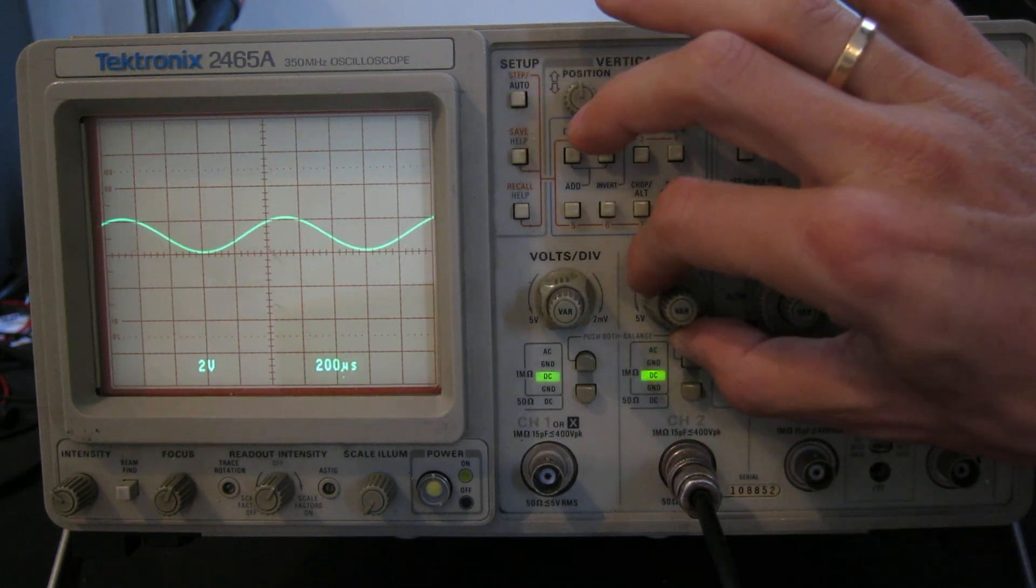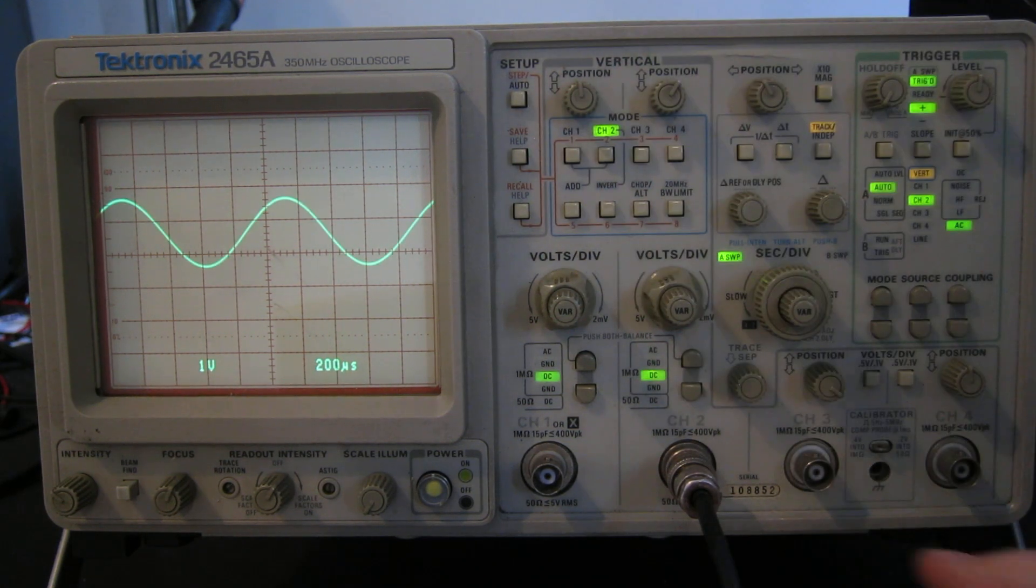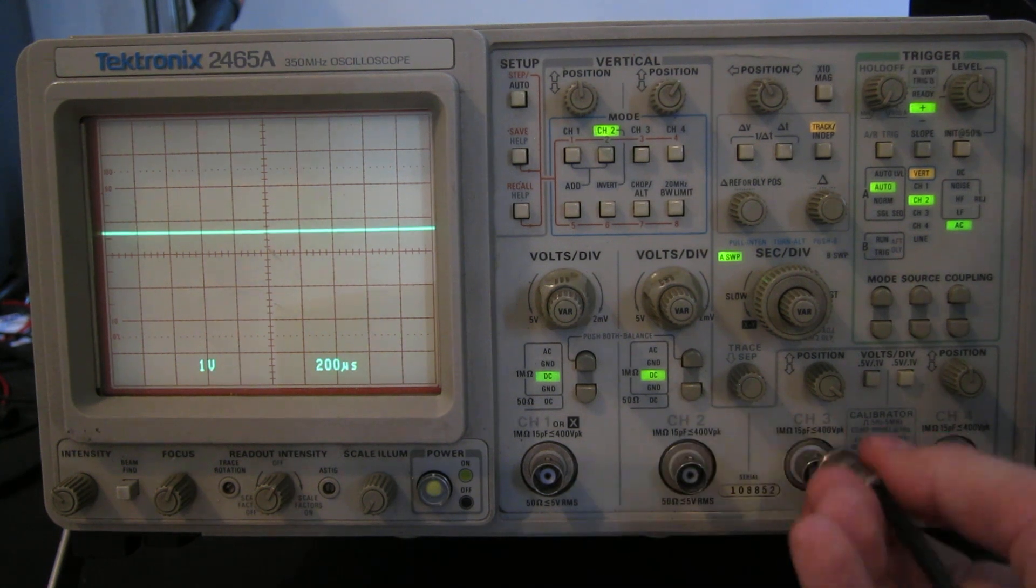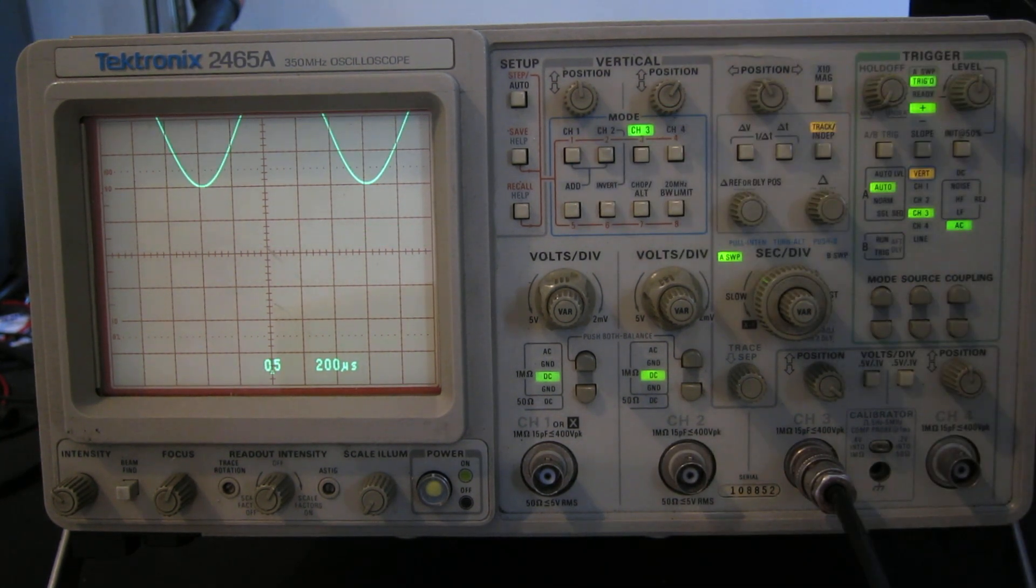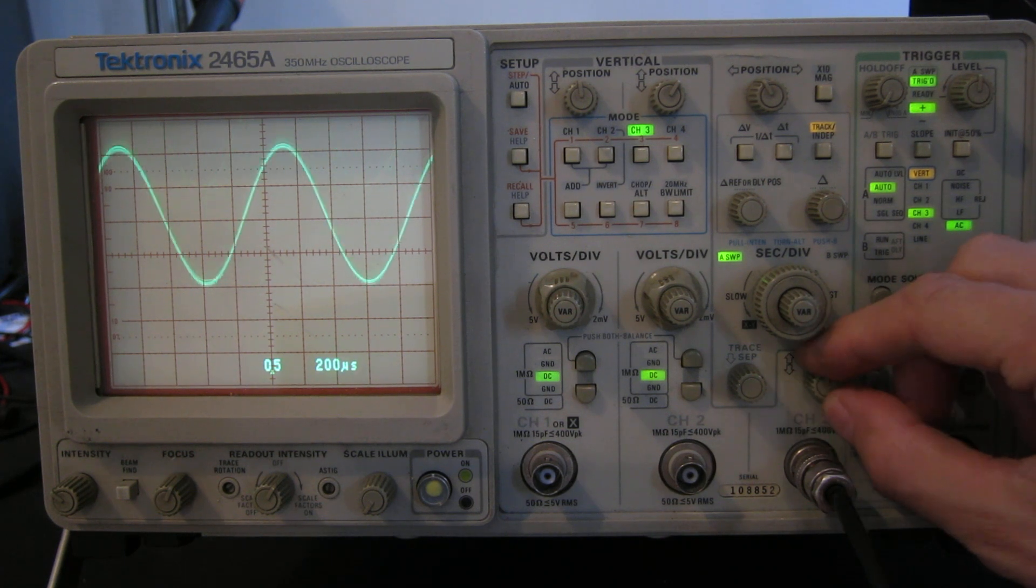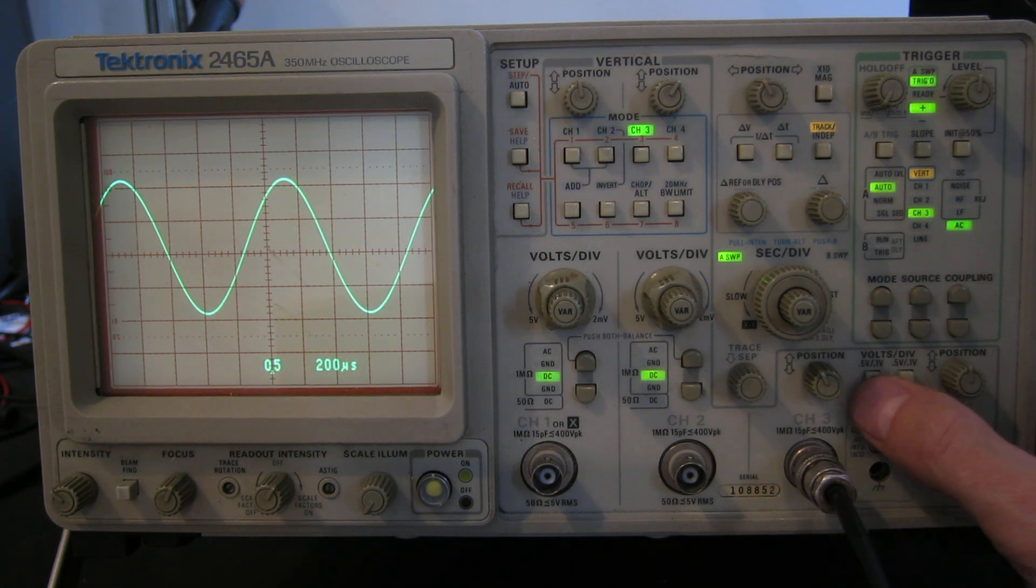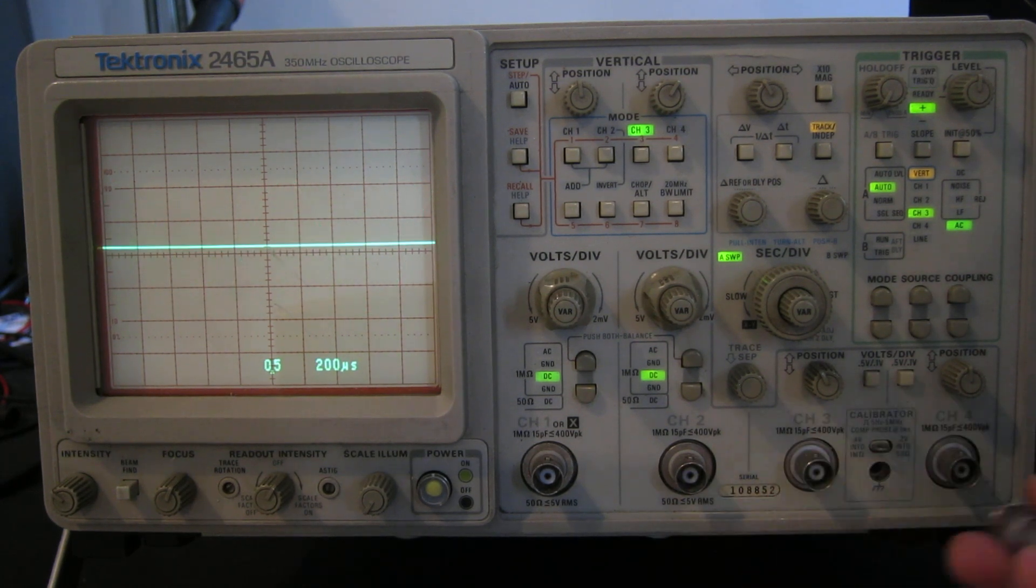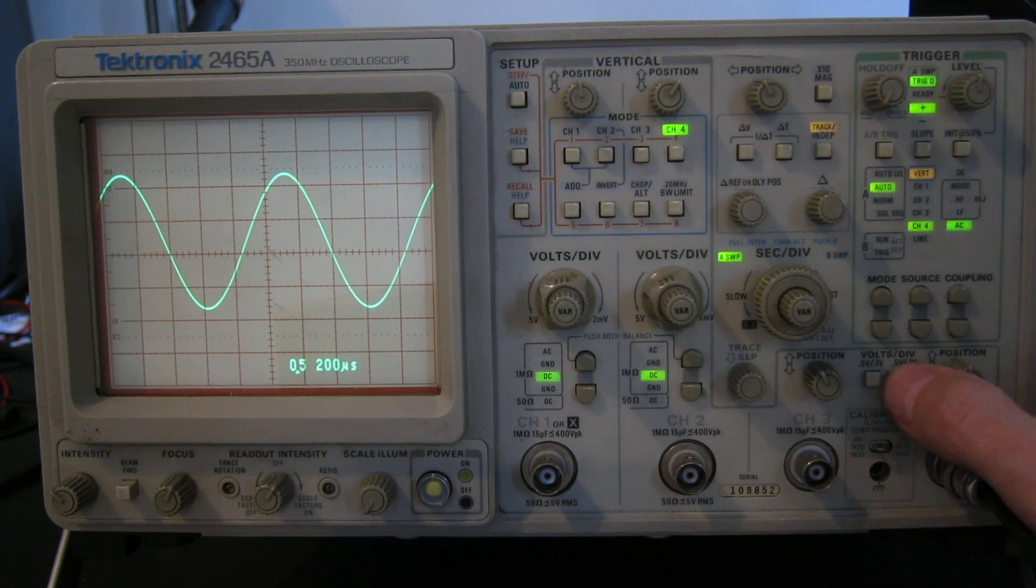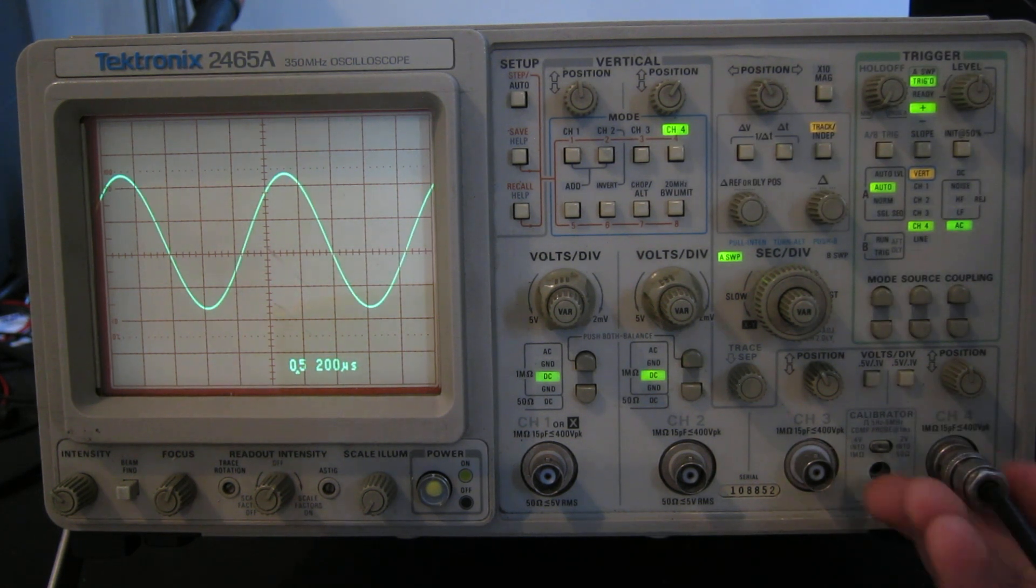Same thing. Move it into view. Attenuator works as you'd expect. Channel 3 and 4 don't have such comprehensive attenuator settings, but they do work. Here we go. That's channel 3. It's got two settings, 0.1 volts per centimeter and 0.5 volts per centimeter. Channel 4, likewise, just the same, works fine.